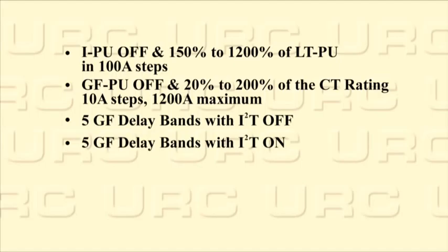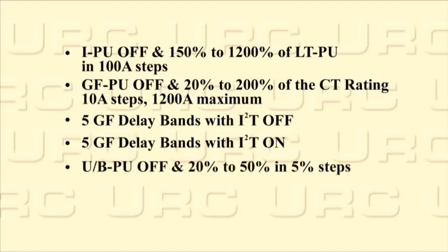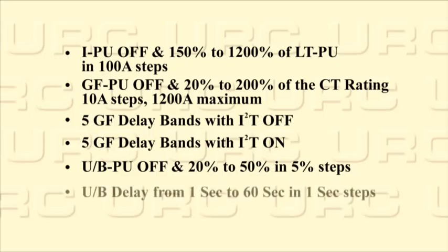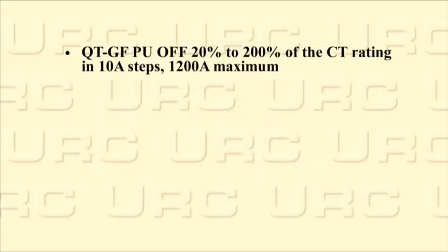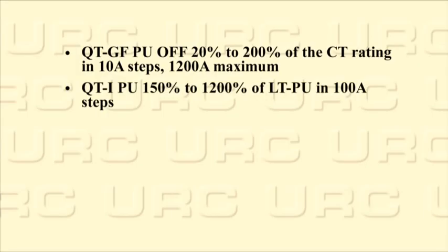The phase unbalance function is based on breaker currents and is used for motor anti-single phasing protection. The unbalanced pickup can be set from 20% to 50% in 5% steps with an off setting. The unbalanced delay can be set from 1 second to 60 seconds in 1 second steps. The quick trip ground fault pickup can be set from 20% to 200% of the CT rating in 10 amp steps with a maximum of 1200 amps. An off setting is available. The quick trip instantaneous pickup can be set from 150% to 1200% of the long time pickup setting in 100 amp steps. An off setting is not available.